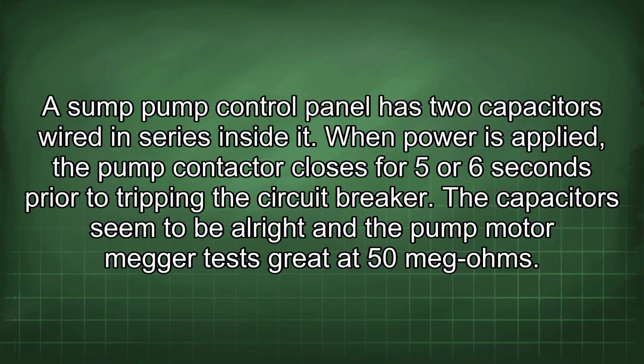The sump pump control panel has two capacitors wired in series inside it. When power is applied, the pump contactor closes for 5 or 6 seconds prior to tripping the circuit breaker. The capacitors seem to be alright and the pump motor megger tests great at 50 megohms.